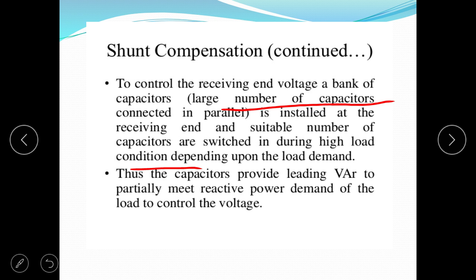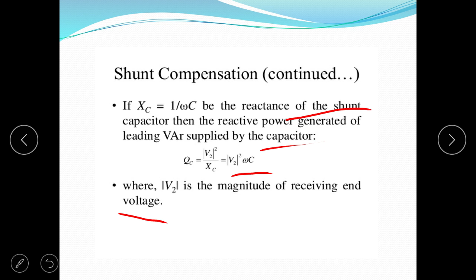Now in shunt compensation, if Xc equals 1 upon omega C is the reactance of the shunt capacitor, then the reactive power generated, the leading var supplied by the capacitor, is Q, written as V2 square upon Xc, that is V2 square times omega C, where V2 is the magnitude of the receiving end voltage. It means a shunt capacitor injects reactive power according to the change in voltage at the receiving end.